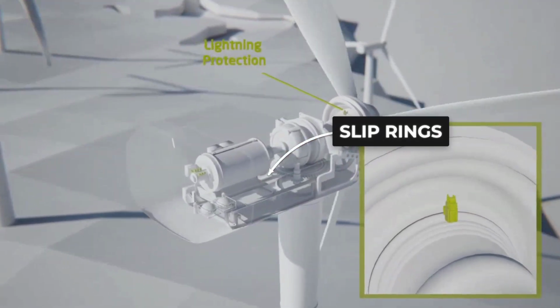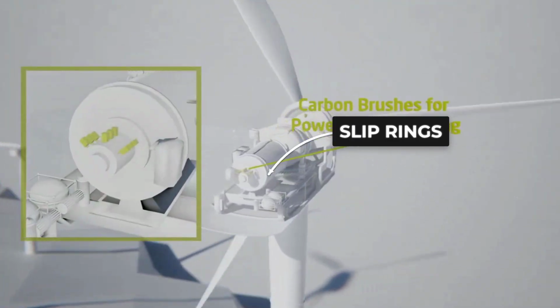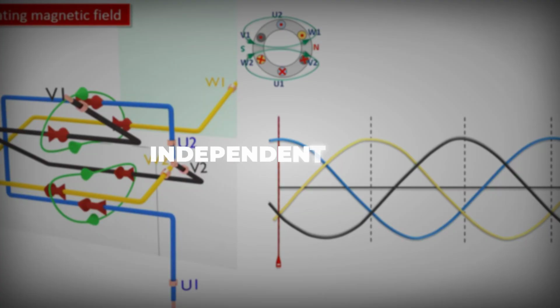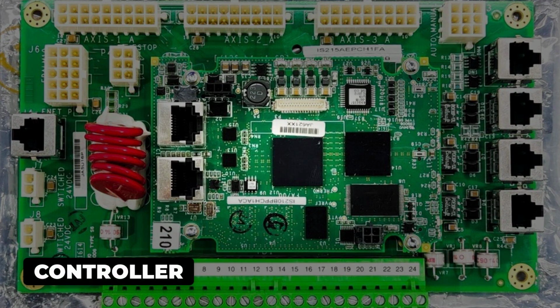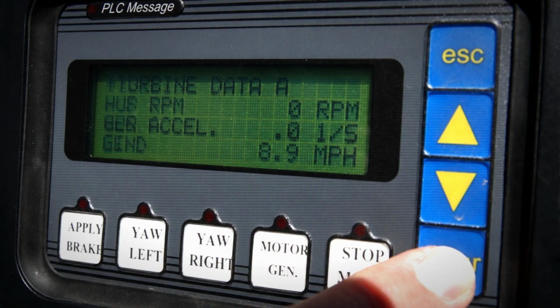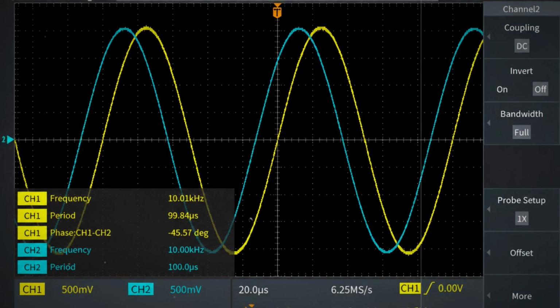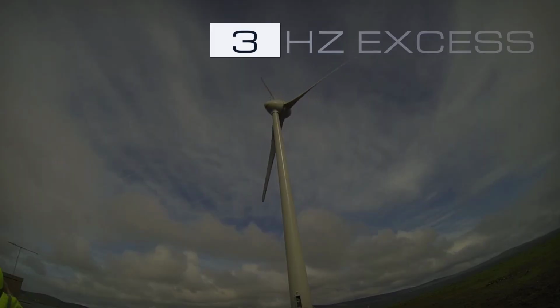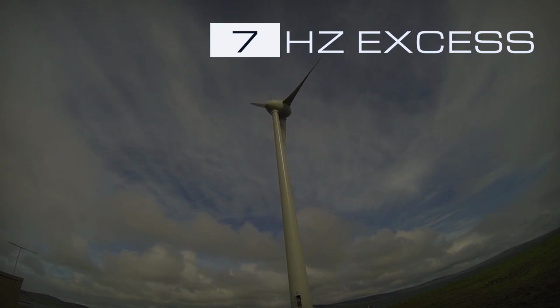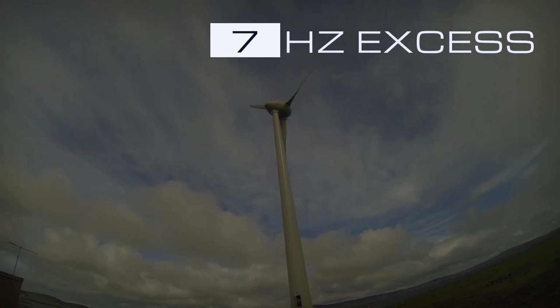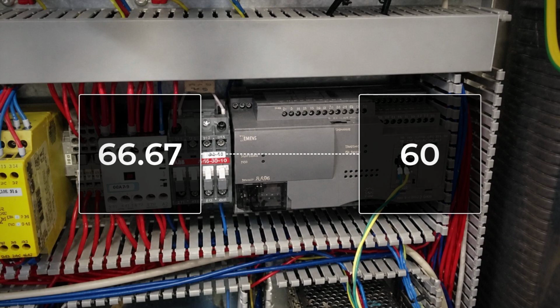A controller fights to close the gap. Through slip rings mounted on the rotor shaft, it injects a separate current into the rotor's copper coils, creating a magnetic field that spins independently of the rotor itself. When the rotor runs too slow, the controller's field spins forward, adding the missing frequency. At 1,700 revolutions per minute, it supplies exactly 3.33 Hz, and the stator output hits 60 Hz. When the rotor overshoots to 2,000 revolutions per minute and produces 6.67 Hz too many, the controller reverses direction, subtracting the excess until the output falls back to 60.